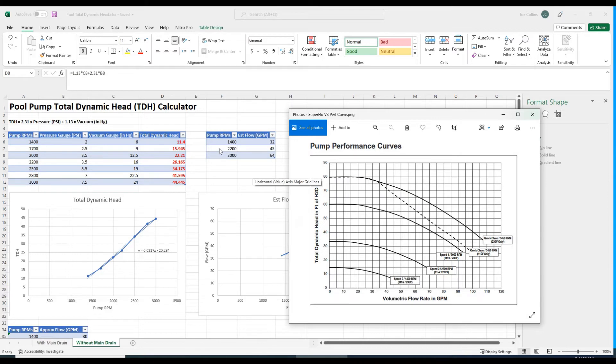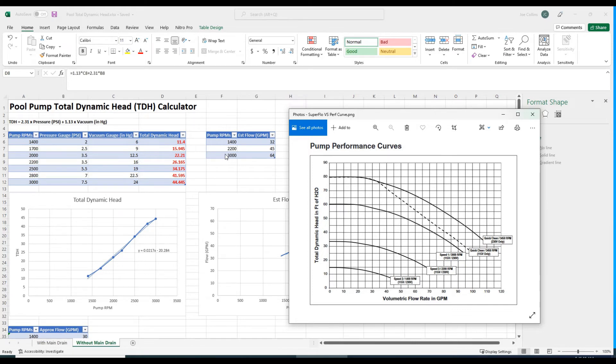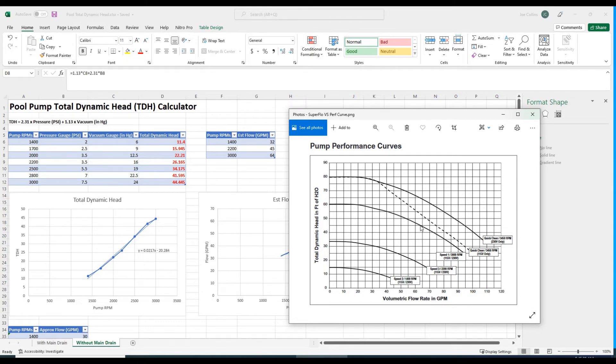At 3000 RPMs, we've got 44 and a half feet of head, call it 45. So 3000 at 45 gives us maybe 64 gallons per minute.